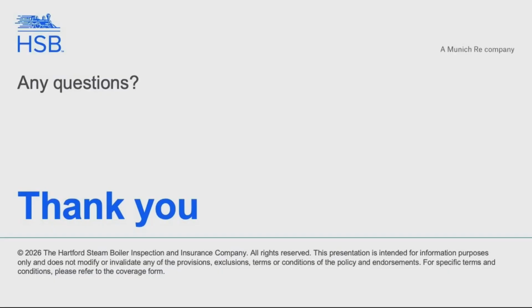Yes. The short answer is yes. It can be certified to ADR, provided the tank is certified to ADR and that country's regulations, and it meets some additional requirements per US DOT regulations. What that means is the design and manufacture has to be to ASME Section 8 Division 1, or if it's going to be other than Section 8 Division 1 for the design and manufacture, it would need a US DOT special permit. But for the most part, yes, and a US DOT designated approval agency is not required. Everything is done per the country of approval, Ireland in this case, and the ADR.